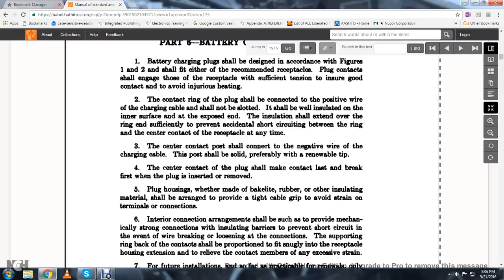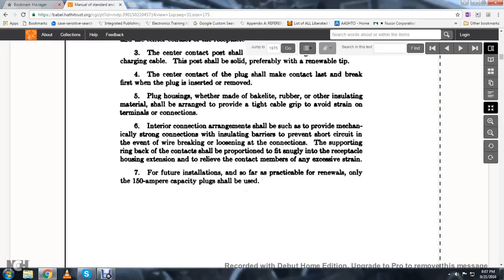The center contact post shall be connected to the negative wire of the charging cable. This position should preferably have a renewable tip. The center contact of the plug shall make contact last and break first when the plug is inserted or removed. The plug housing, whether made of hard rubber or other insulating materials, should provide a tight gripping handle to avoid strain on terminal connections. Interior connection arrangements shall be provided with mechanically strong connections, insulating barriers to prevent short-circuiting, and support the ring back of the contact.